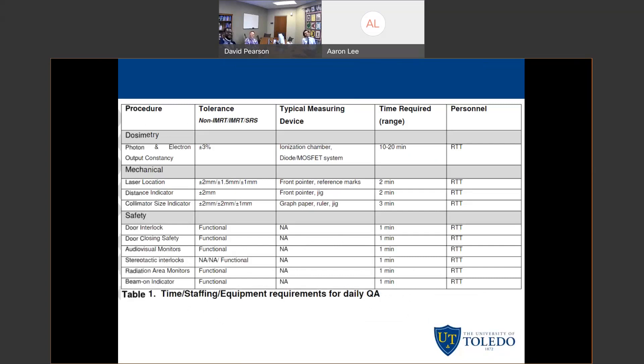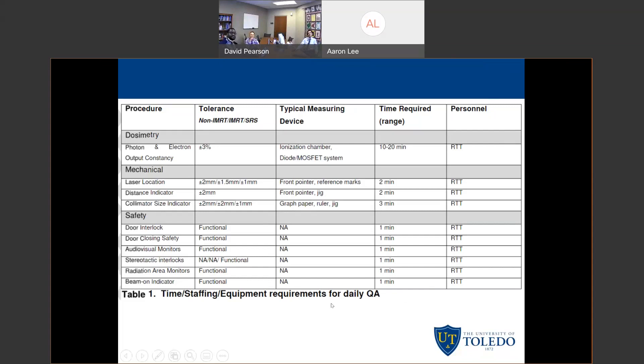Now going through the tables at the end of the report, they very nicely outline every single test, the tolerances, what you can use to measure it, how long it should take, and who should be performing it. For the daily QA, you can see all of the safety checks, mechanical tests, and output constancy measurements, where you can use some kind of ion chamber or diode system. It also budgets the time so you can go to administration and say this is how long it takes us to do these things — it may be unreasonable to ask us to do them more quickly and still feel we are doing a thorough, safe job.